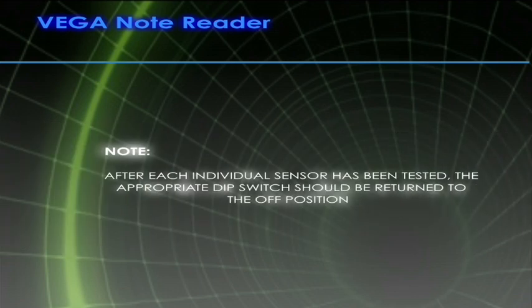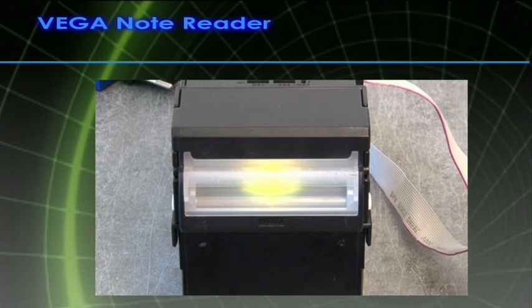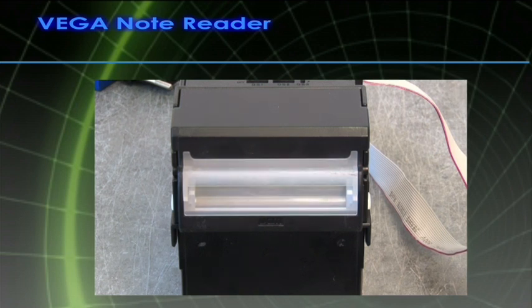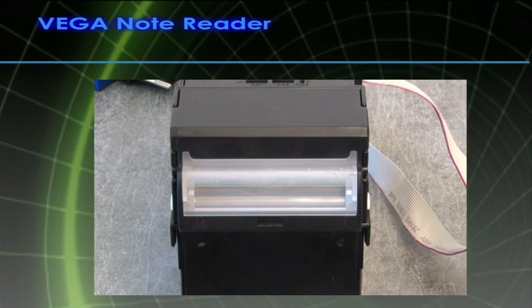After each individual sensor has been tested, the appropriate dip switch should be returned to the off position. That's to say, when the switch number 1 test has been performed successfully in the on position, it should be reset to the off position before undertaking any further action. When the selected sensor detects an object, such as a banknote or a test paper, the front panel LED will show yellow color. When there's no object detected, the front panel LED display will be out. This completes the sensor test.